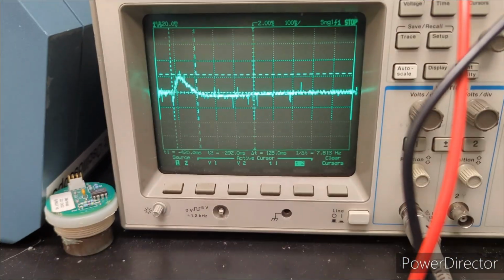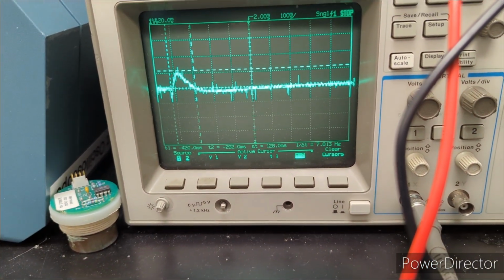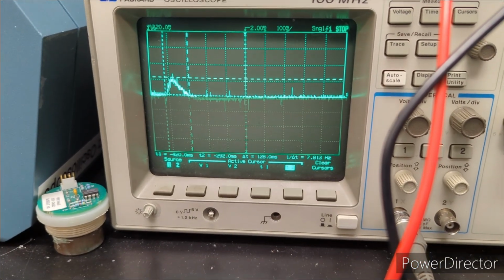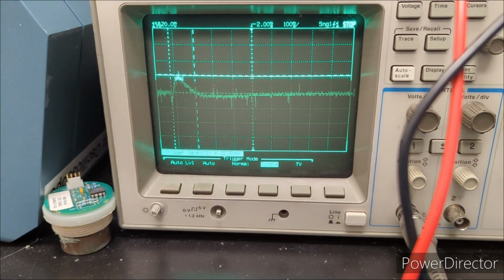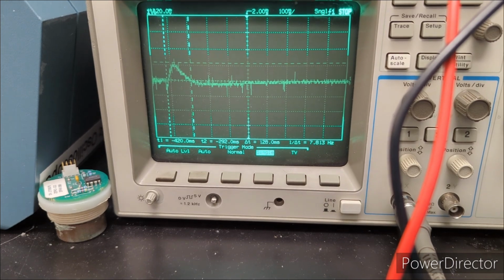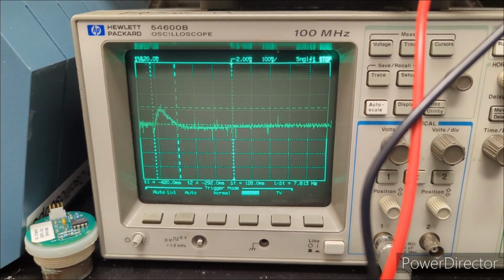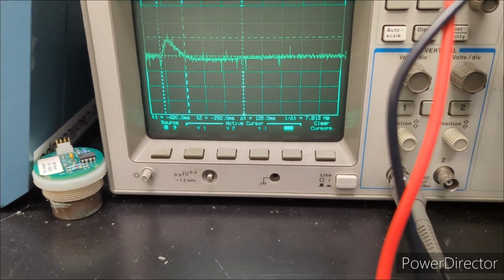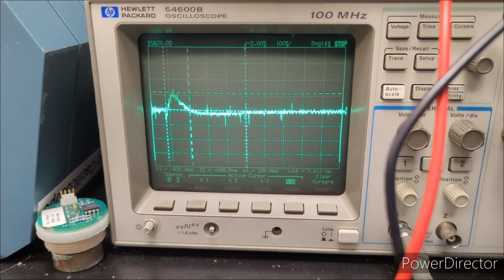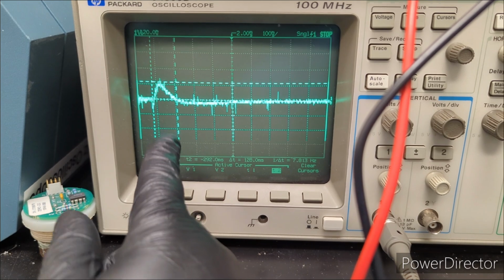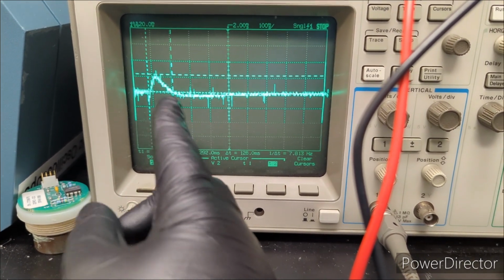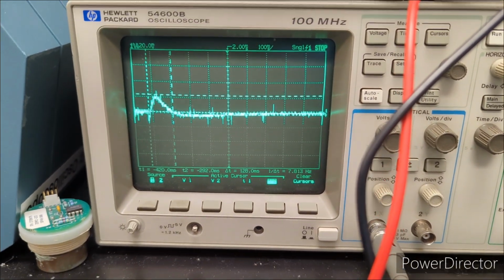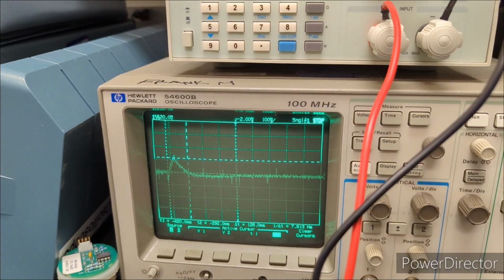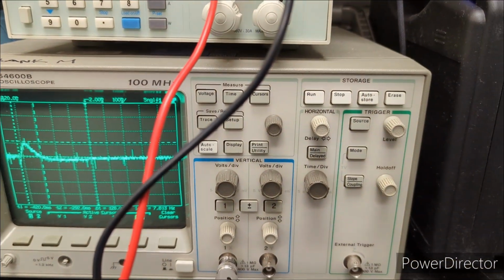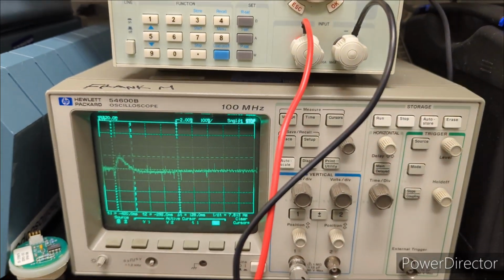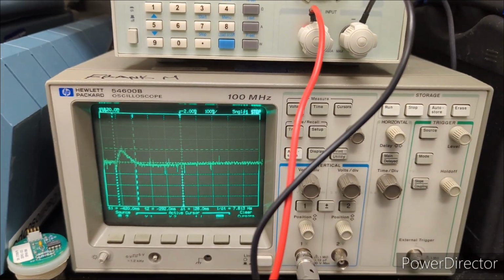And so what I'm doing here is I'm using the single trigger mode on the instrument. So if you look here, if I click mode, it's listed as single, so it'll take a single snapshot of the waveform. And then what I was displaying earlier was the cursor measurements, so that way I can measure the time from the rise and the fall of the peak, and also the peak-to-peak voltage. So that's what we're going to do. And so what I'm going to do is turn the load on and press the run button at exactly the same time, so it should capture the waveform, that transient recovery peak.